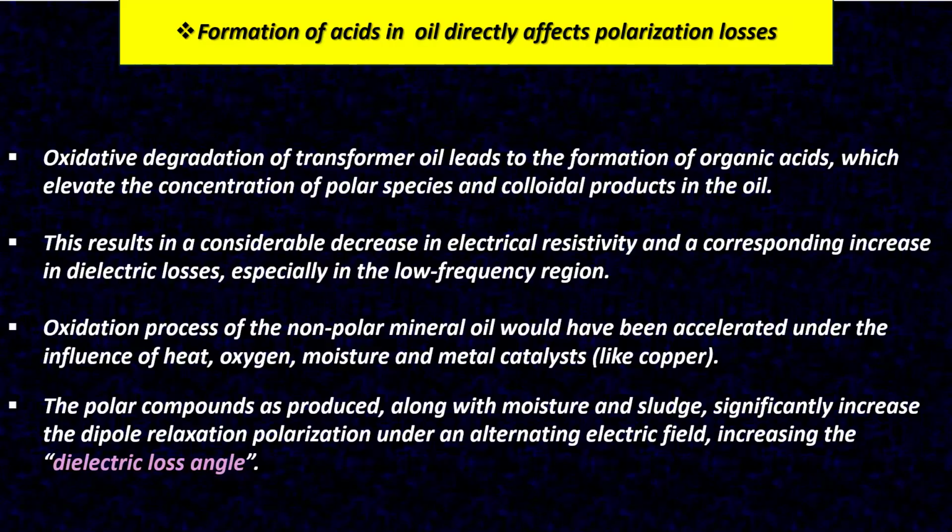Let's start with the formation of acids in oil, which directly affects polarization losses. Oxidative degradation of transformer oil leads to the formation of organic acids, which elevate the concentration of polar species and colloidal products in the oil.